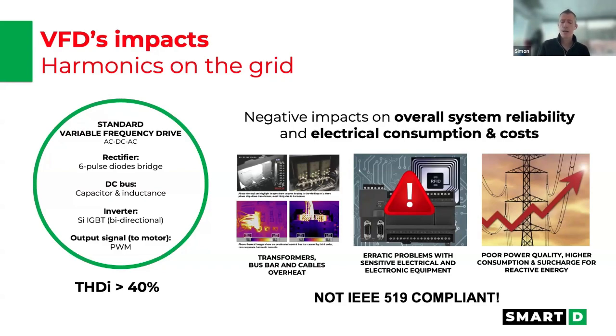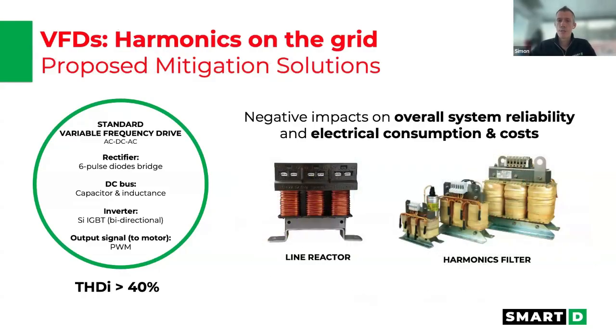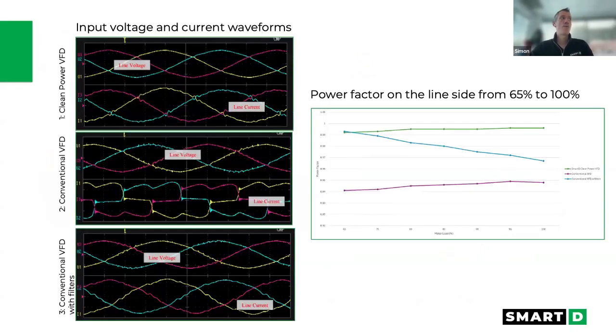So in North America, it's IEEE 519 that might mandate you to keep that harmonic content low so that you don't start polluting other equipment on the grid with your own harmonics. Typical mitigation, as you know, is a line reactor or harmonic filter. Let's look right away at how a harmonic filter compares to a SmartD clean power VFD.